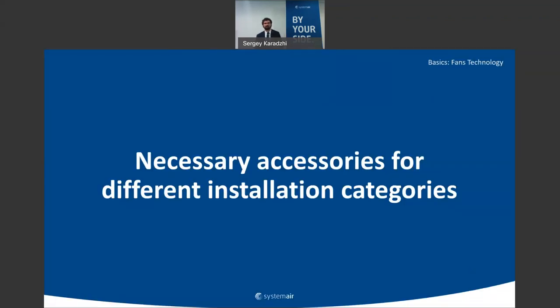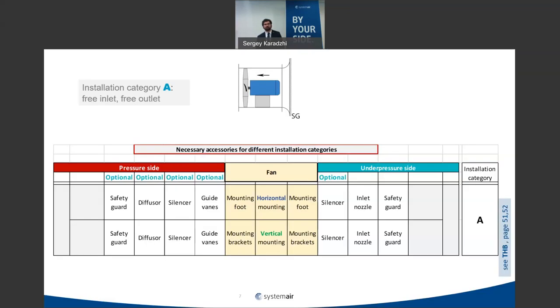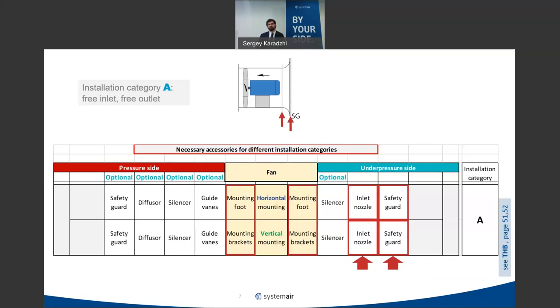Regarding necessary accessories for different installation categories: for free inlet, free outlet (Category A), you need an inlet nozzle and safeguard for safety reasons, mounting feet with dampers to isolate fan vibrations from the base, and ideally a diffuser on the outlet to recover dynamic pressure. Silencers and safeguards on the outlet are optional depending on sound level requirements.